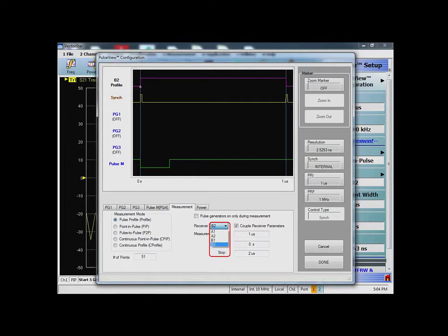having independent receivers is a good option, because normally in the measurement world today there are not a lot of VNAs which can have independent receivers. Normally, say suppose you have a DUT which adds a lot of delay in your pulse.